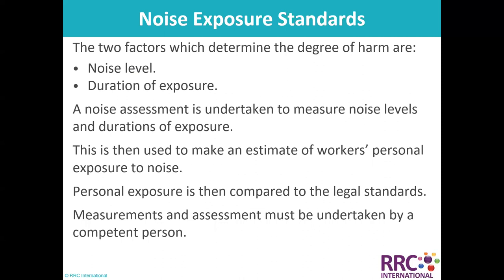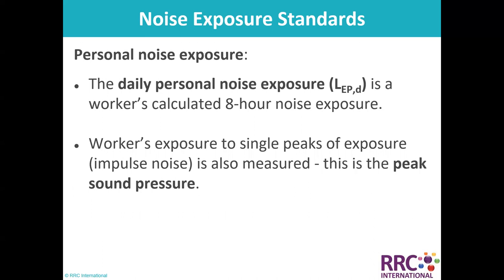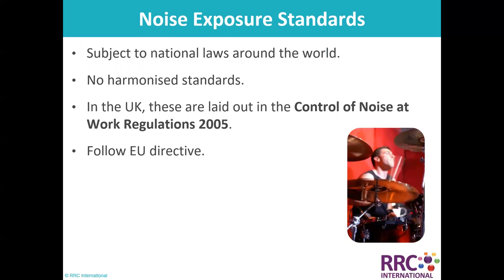Noise exposure standards: the two factors that determine the degree of harm are noise level and duration of exposure. This is used to estimate workers' personal noise exposure, which is then compared to the legal standard. Measurements and assessments must be undertaken by a competent person. Personal noise exposure is calculated as a worker's eight-hour noise exposure (LEP,d). Exposure to single peaks of impulse noise is also measured as peak sound pressure.